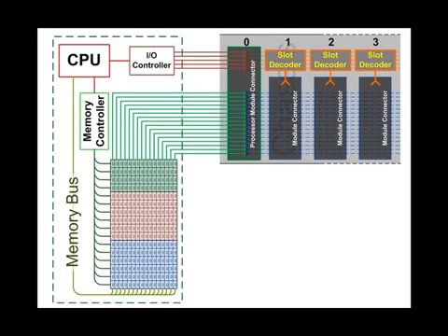For the sake of simplicity, we are limiting the components of the processor module in this diagram just to those that we need for this discussion. The two primary connections of interest to us are the data bus in green and the control bus in red. Now, by means of the I/O controller, the CPU sends an encoded binary signal down the length of the control bus to affect a slot decoder to activate the slot of interest to the processor.